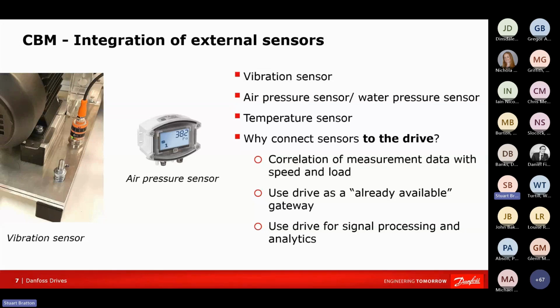The reason that we want to connect the sensor to our drive is that it gives us the ability to correlate the measurement data, let's say it's vibration, with the speed of the motor. If we were to use an externally mounted sensor on the load, for example, it may not necessarily be aware of the speed the motor's rotating. It's just arbitrarily measuring vibration levels. But with the sensor connected to the drive, it can record, as I mentioned earlier, a baseline: the normative recording of the expected sensor signal for a range of motor speeds. And as I've said before, the drive can then process that data in some way.